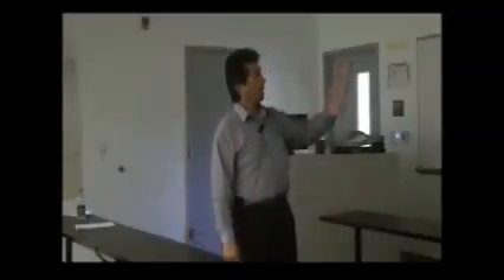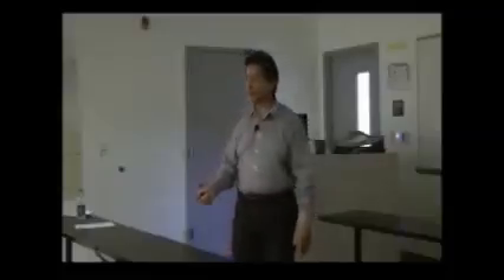Okay, this one here, I knew that was going to do that, so we'll go on to that one there. So dielectric losses and power factors I was mentioning a little bit before. Whatever you do in power, you're going to have some sort of resistance and some sort of losses. So if I'm getting a full 208, 480, I'm going to have some sort of losses just based on the nature of power as I'm running it through my conductors and medium. Increases in loss again is going to have some sort of potential failures. That means somewhere along the line I've got a breakdown in insulation.